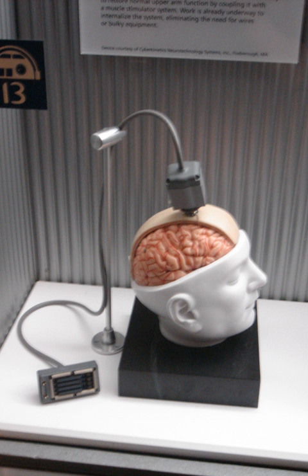Neural implants are designed to be as small as possible in order to be minimally invasive, particularly in areas surrounding the brain, eyes or cochlea. These implants typically communicate with their prosthetic counterparts wirelessly. Additionally, power is currently received through wireless power transmission through the skin. The tissue surrounding the implant is usually highly sensitive to temperature rise, meaning that power consumption must be minimal in order to prevent tissue damage. The neuroprosthetic currently undergoing the most widespread use is the cochlear implant, with over 300,000 in use worldwide as of 2012.